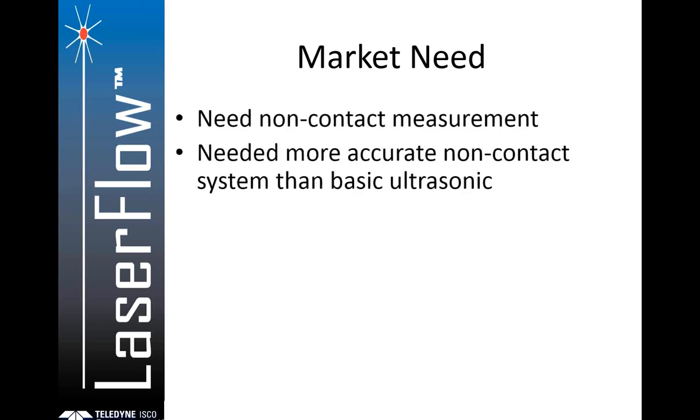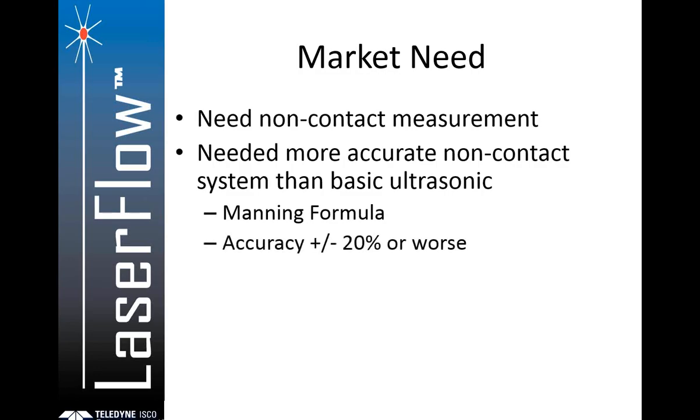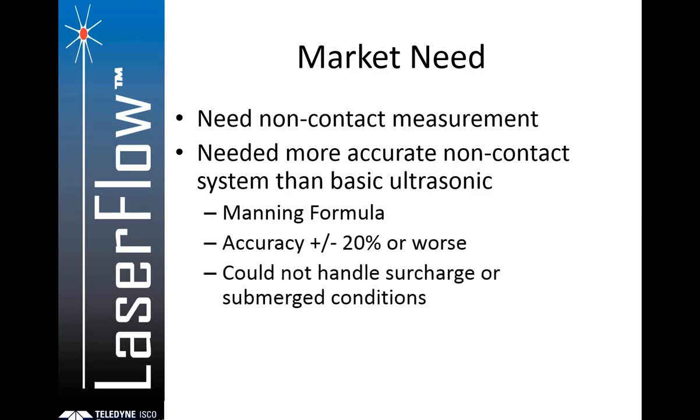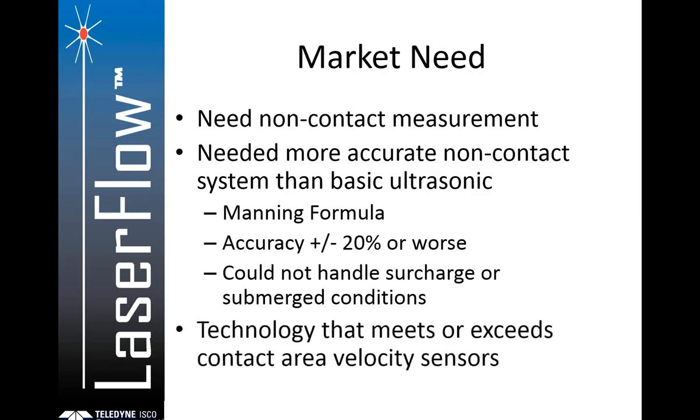So the market need drove the advancement of non-contacting measurement for more accurate data than basic ultrasonic sensor using the Manning formula, which the literature says can have an accuracy of plus or minus 20% or worse, and there was no way to handle surcharge or submerged flow conditions. So we want a technology that meets or exceeds contact area velocity sensors in all of these areas.